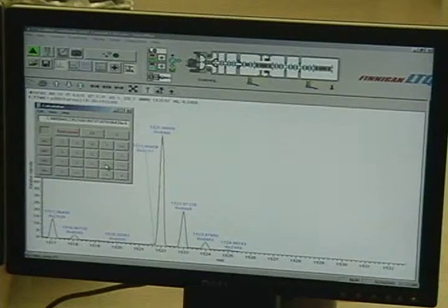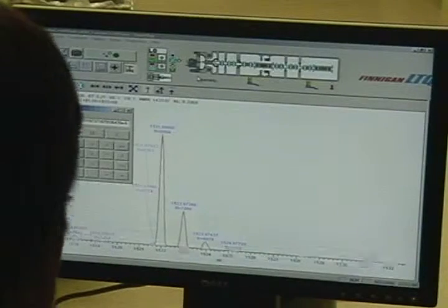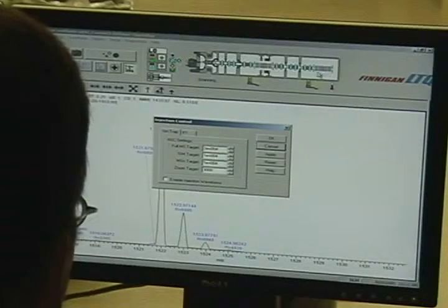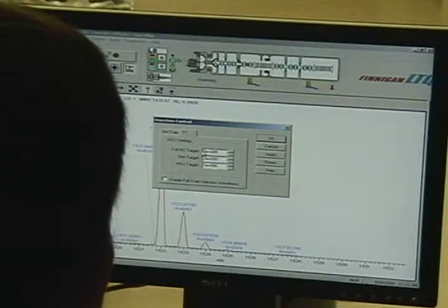Okay, we're at 1.9 ppm. So sub 2 ppm is the goal? Sub 2 ppm is the goal. I make my measurements at sub 2 ppm for 5E5.